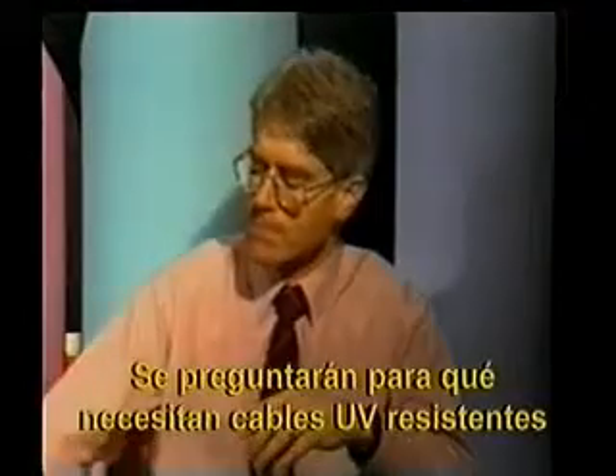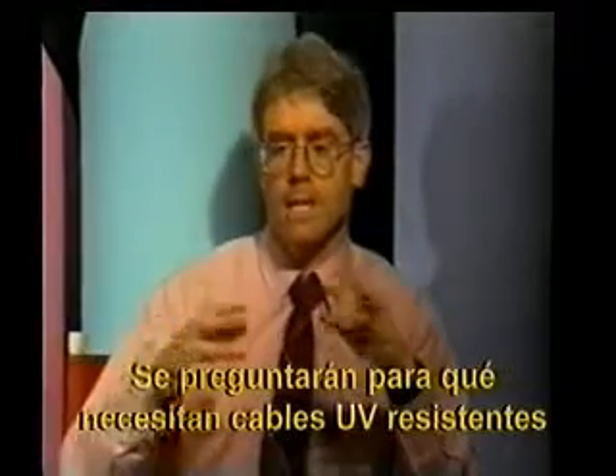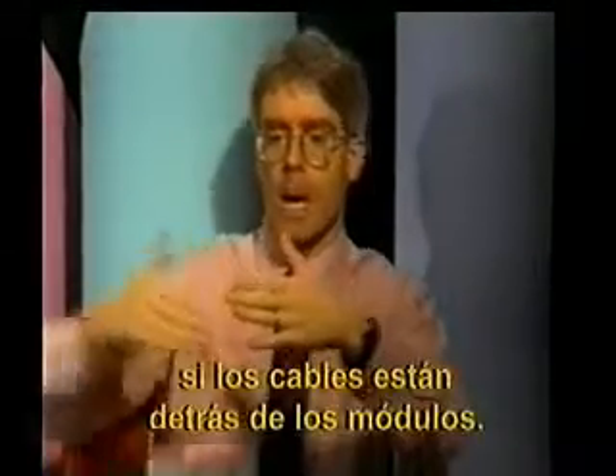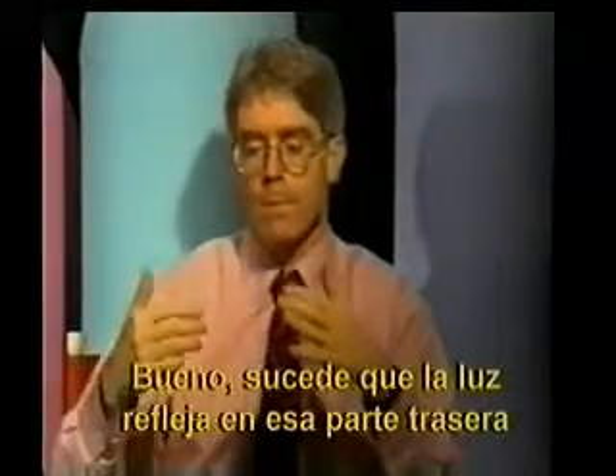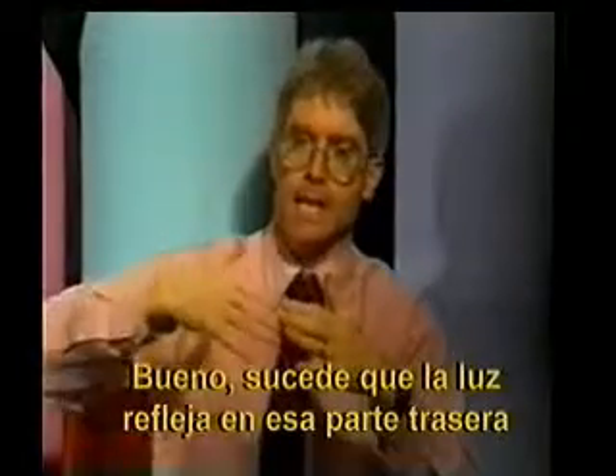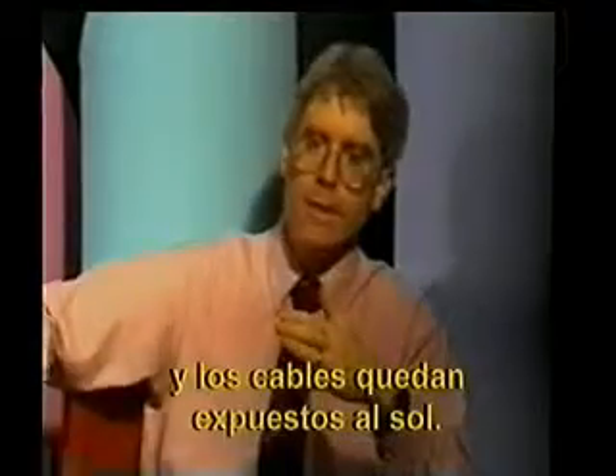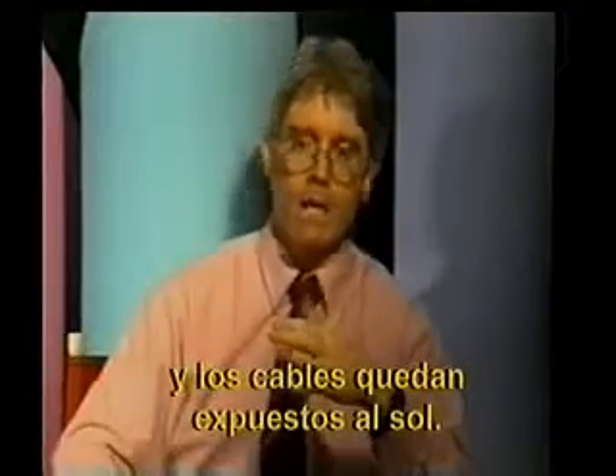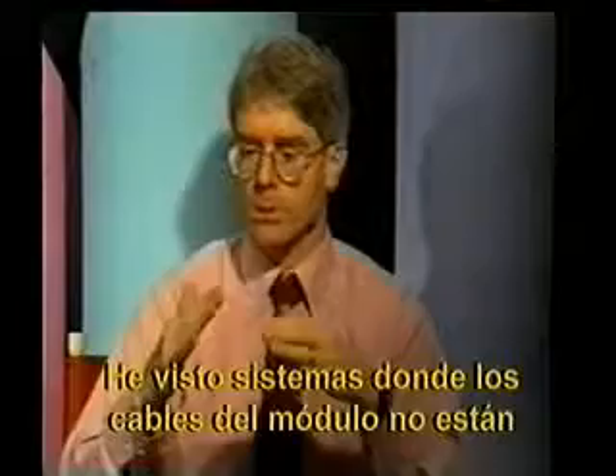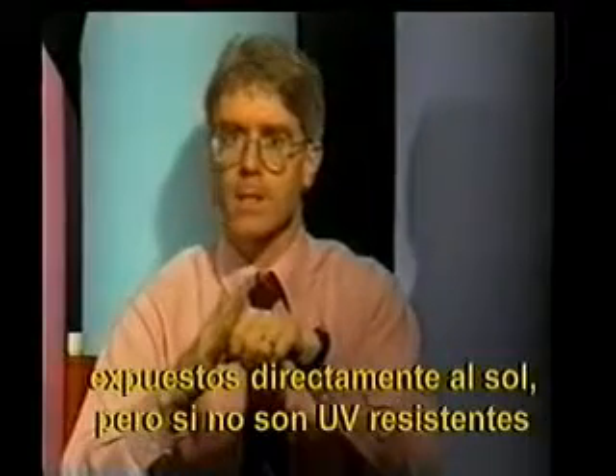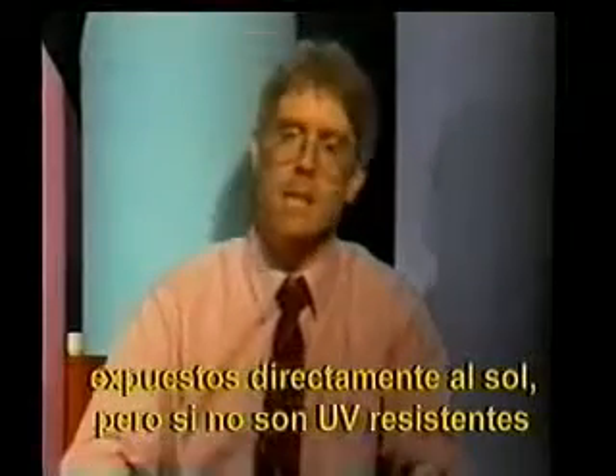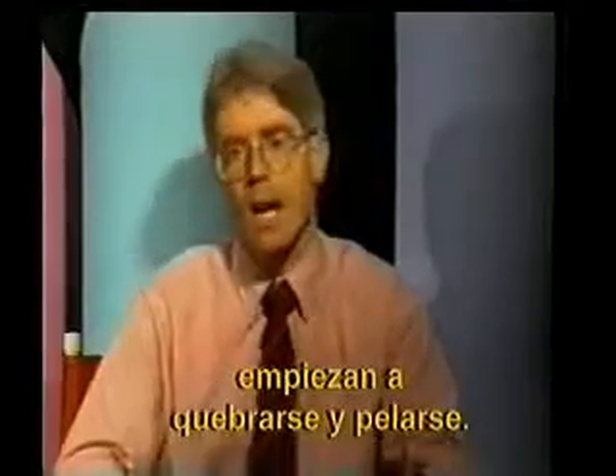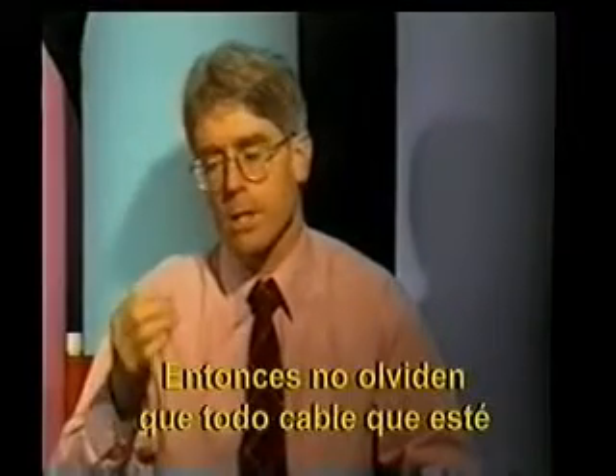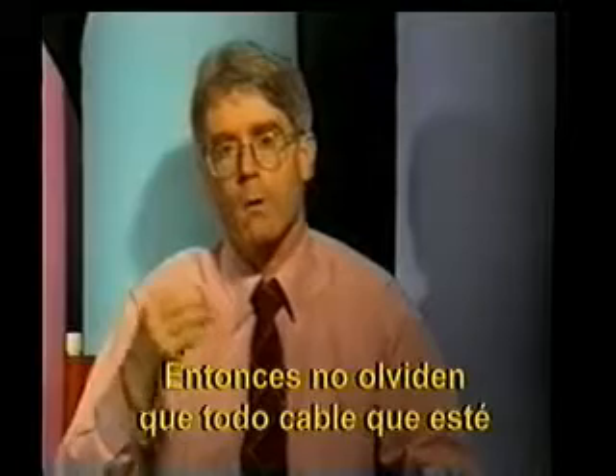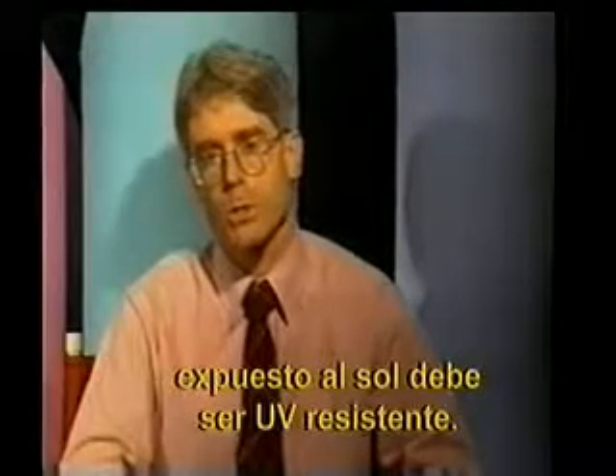You might say to yourself, why do I need sunlight resistant wire if the wire is behind the module? Well, you get reflected light to the back of the modules, and all that ultraviolet light is reflecting onto that wire. So I've seen systems where the module wiring is away from direct exposure to the sun, but if it hasn't been sunlight resistant, it's already starting to crack and peel. So make sure that you choose sunlight resistant wire for any wires that might be exposed to sunlight.